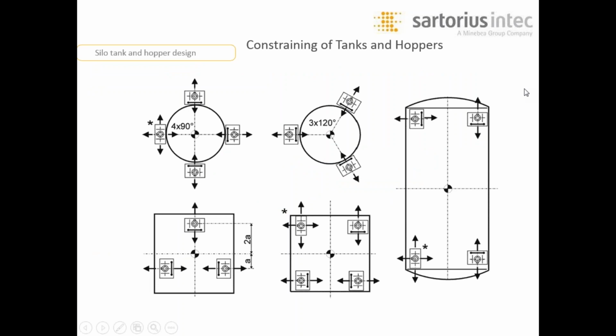Mounting kits with constrainers protect from structural damage and weighing errors. Depending on the number of legs and the forces to be expected, the configuration can consist of constrained and non-constrained mounting kits. For vessel scales with 3 legs, 3 constrained kits are generally recommended. For vessel scales with 4 legs, 3 constrained and 1 non-constrained is recommended, simply because it will avoid any type of binding within the system. A wind and earthquake calculation tool can be used to support the selection of the particular mounting kits.